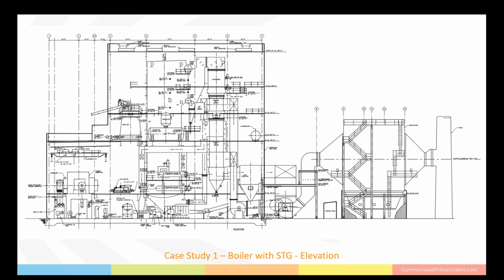The elevation of this boiler with STG plant has a couple of things to point out. Above the steam turbine generator is a 20-ton bridge crane with a 5-ton auxiliary hoist for the rotor and condenser pull. The elevation of the wood bin that feeds the screw conveyor for the boiler is partially what sets the distance between the reclaim hopper and the power plant itself. There are accommodations in the roof for ventilation. As mentioned before, you can see the access platforms on the precipitator for the inlet duct and outlet duct access, as well as performance sampling in the vertical section of duct.